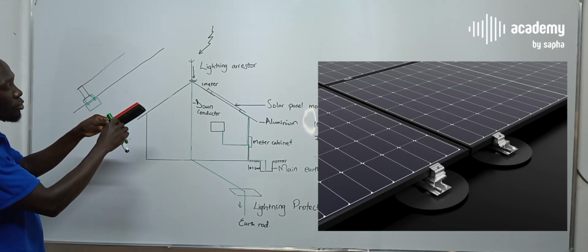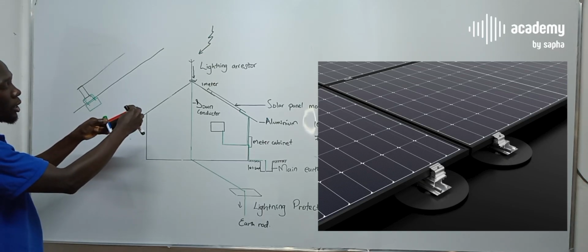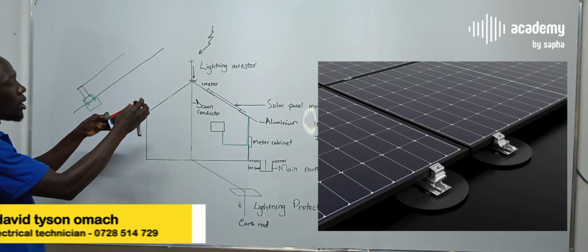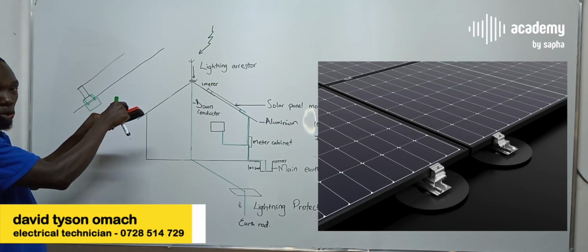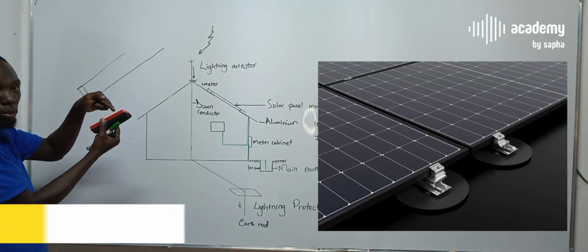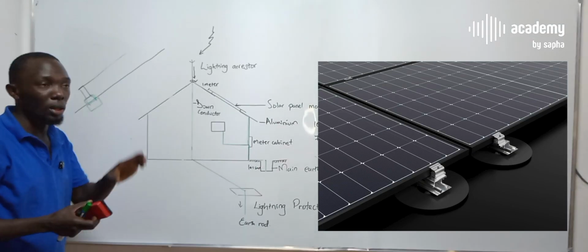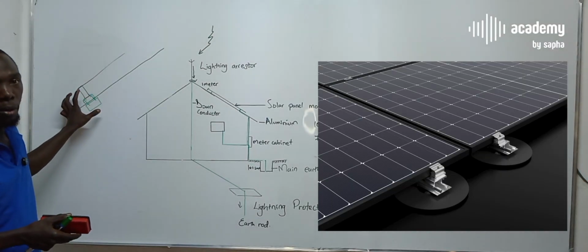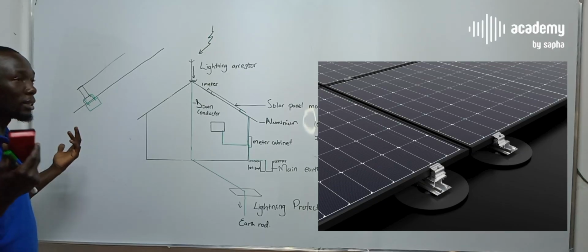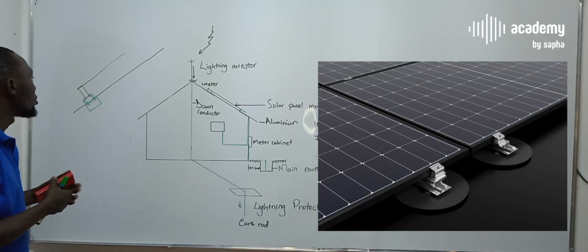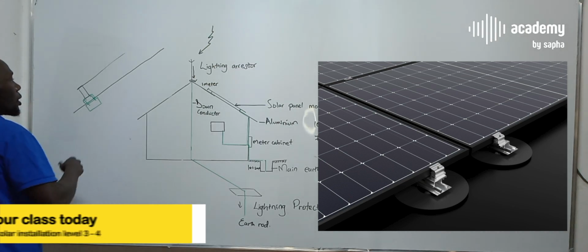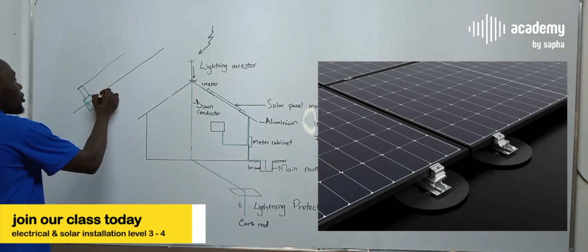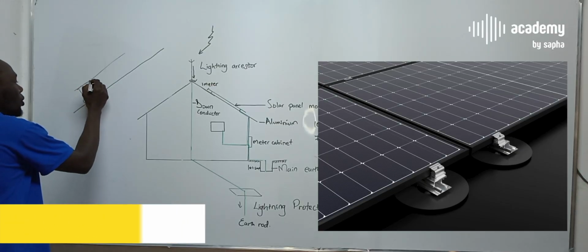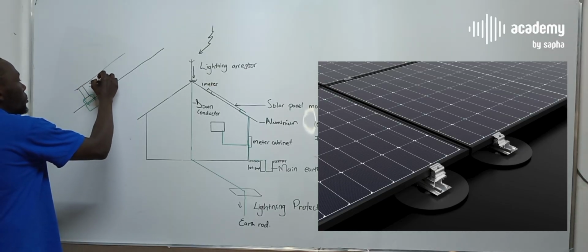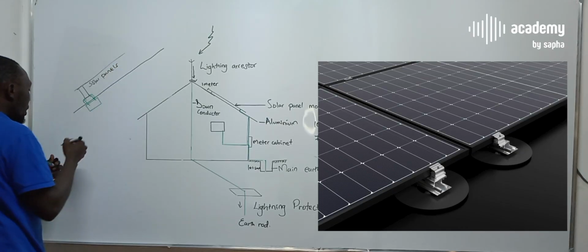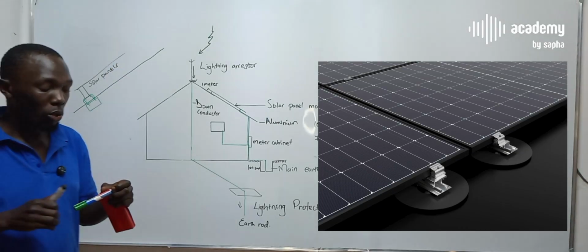So you have two sets of screws: the first set screws the insulating material to the iron sheets, and then when the aluminum frames settle on top of this insulating structure, you screw them in. You need something a bit thicker to allow this to happen. That allows proper insulation between the roof and the metallic or aluminum structure of the solar panels. That is one thing to remember.